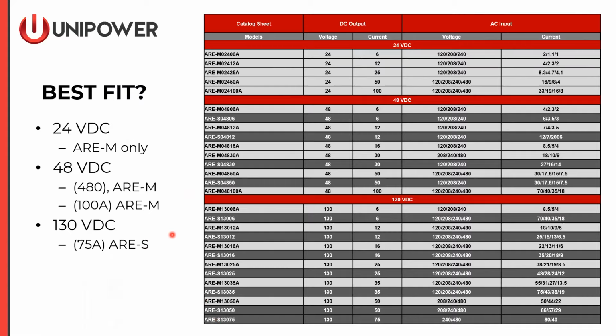Well, yeah, the Ferro Resonant chargers are basically a simpler design. It's going to have a lower parts count, even though the material costs may be slightly higher. The Ferro Resonant charger has, to regulate the output, for instance, a single triac that we gate to regulate the DC output, whereas the SCR control charger is going to have 2 SCRs and 2 diodes in the bridge rectifier. And we have to fire 2 SCRs to regulate the DC output. So lower part count, simpler, basically a simpler deployment, simpler maintenance for the customer that wants a Ferro Resonant charger. For that reason, we see Ferro Resonant in specs. The ARE-S may be slightly less expensive as it uses less material, less iron and copper in those input power transformers.